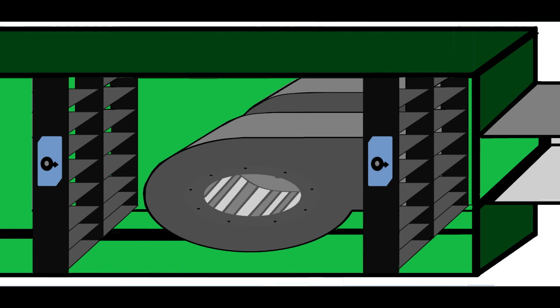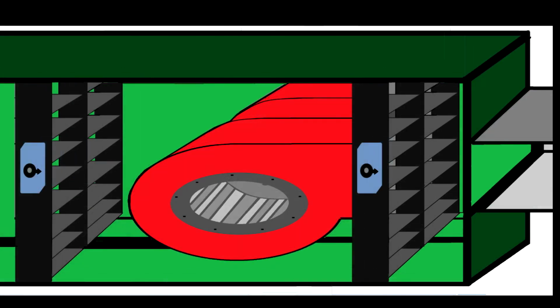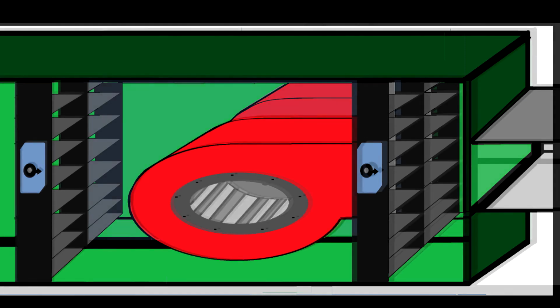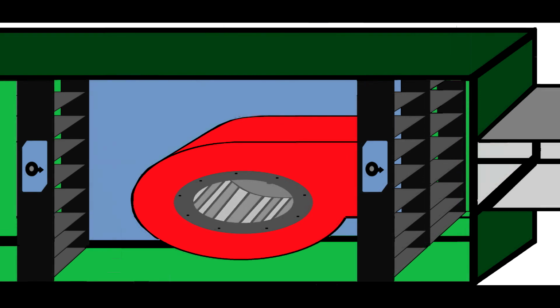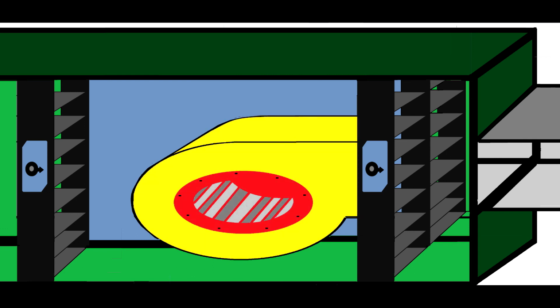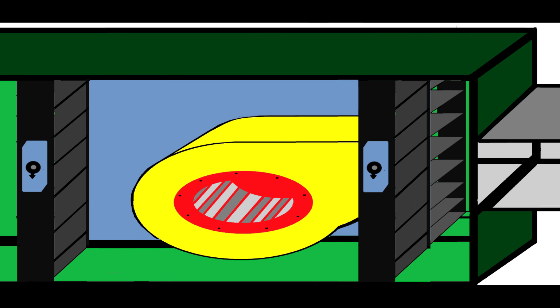Just like the other motors, I said they have pros and cons. These motors are running, but they generate heat inside the supply air chamber. And you have to compensate that heat by running the heat exchanger a little bit cooler. But the beauty about this type of motor, you can segregate the rooms. Each fan will run in its own room. And if one of these fans gets faulty, you will observe the dampers will close and will isolate the area, so you can safely remove the fan to repair, while the other fan will compensate.